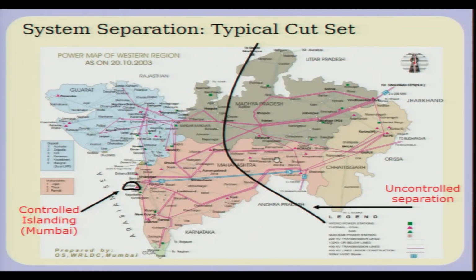In fact, if you have got load generation balance and you separate out into two islands, one of the islands could be under generated, in which case the other one would be having excess generation, because before this disturbance they were balanced. So, once you separate out, they may not be balanced, and there can be a sudden change in frequency, and a sudden change in frequency which is not arrested quickly usually leads to a complete blackout. That happens because if the frequency falls below 47, many of the thermal steam turbine generators trip out, or if the frequency goes above 51 hertz or so, or 52 hertz, they will trip out on overspeeding. So, both at under frequency and over frequency, the generators trip out.